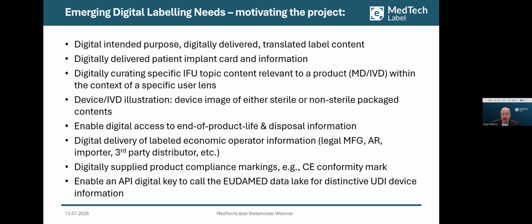And then digitally delivered label economic operator information, typically considered much lower risk as far as what's provided on a printed label. Also enabling the implementation of the new ISO 15223-1 Amendment 1 symbology change for authorized representative in Europe. The digitally supplied compliance markings, the CE conformity marking, being able to provide that digitally rather than directly part marked on devices or through product labeling.